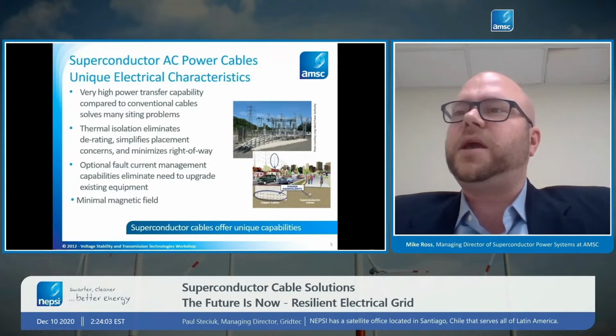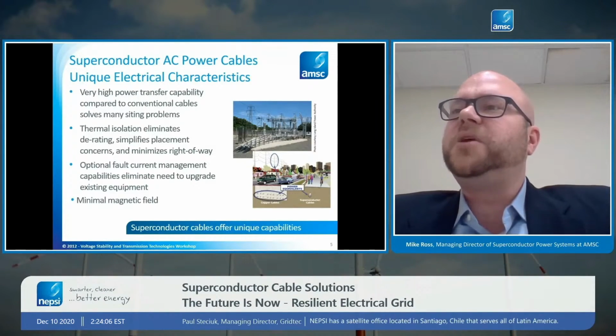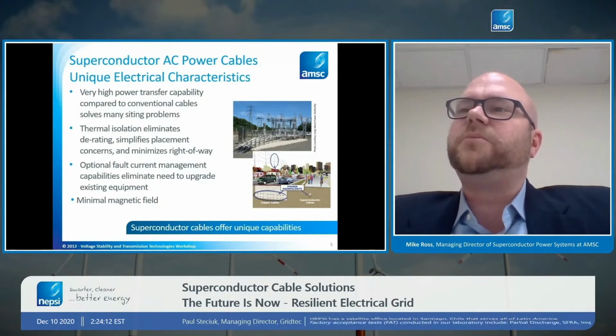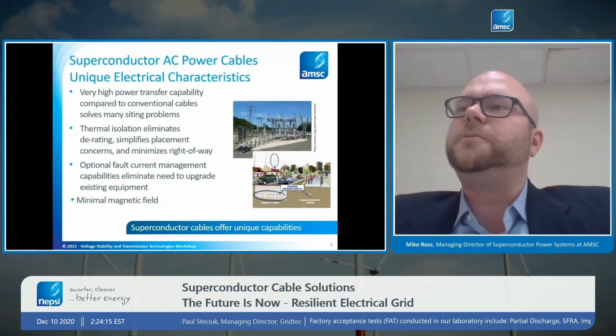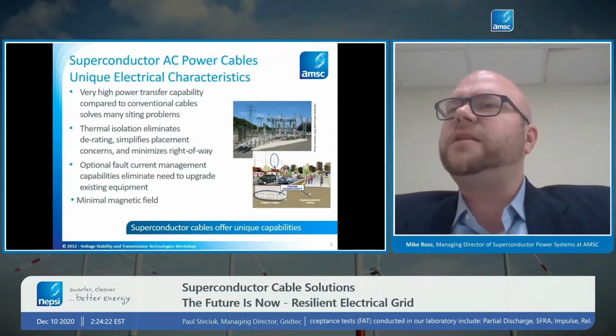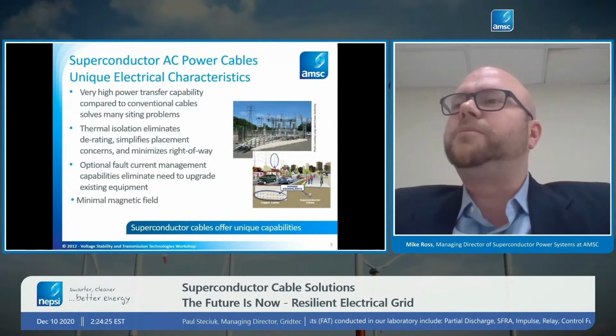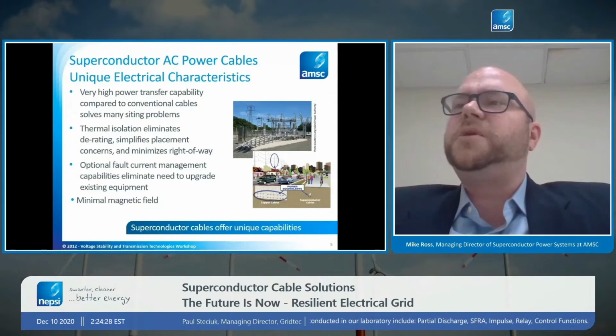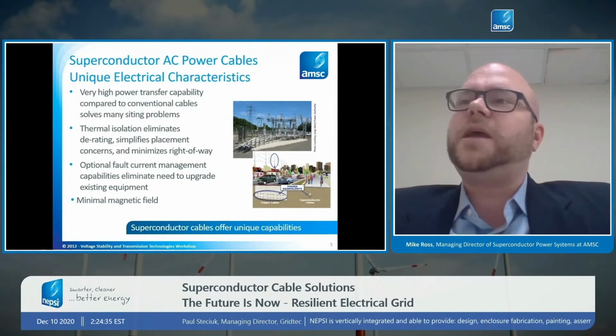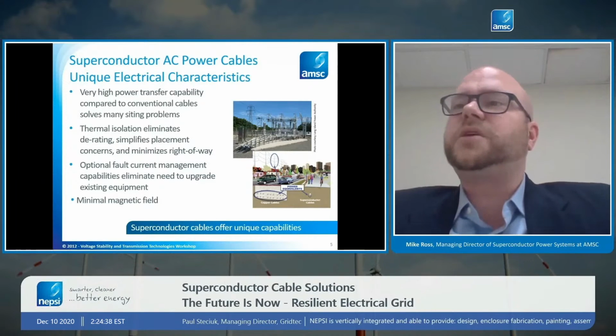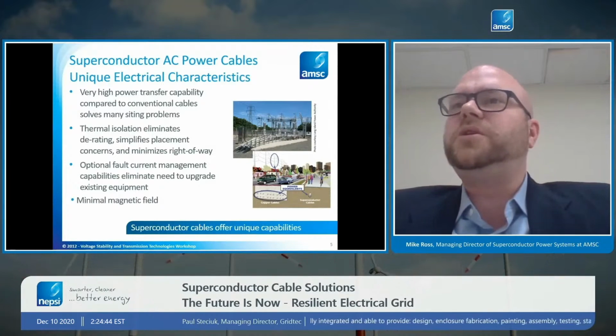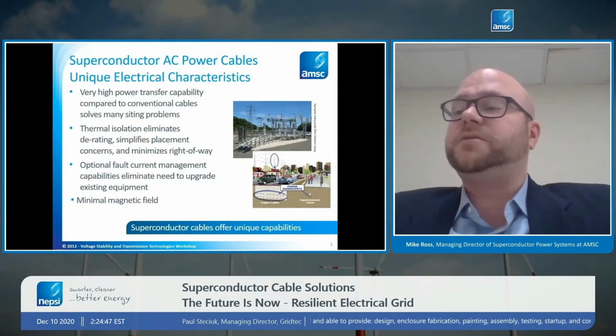For example, if you put a power cable, a conventional transmission cable, near something made out of metal, like a bridge or railroad tracks, the magnetic fields from the power cable will cause current to flow in those metal components, which causes heating and other problems. So very often you're not allowed to put transmission cables on bridges and in other locations because of that issue. With superconductor cables, that problem completely goes away. So you can now put the cables in places where you can't put conventional cables. And this idea of being able to site these cables where previously you couldn't is one of the big value applications of the technology.